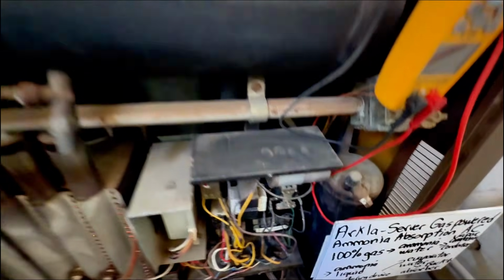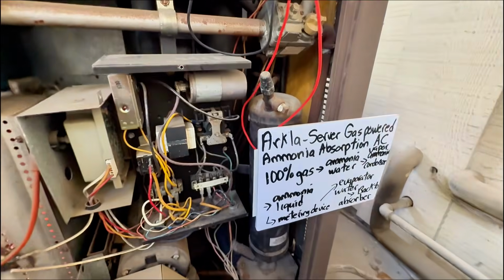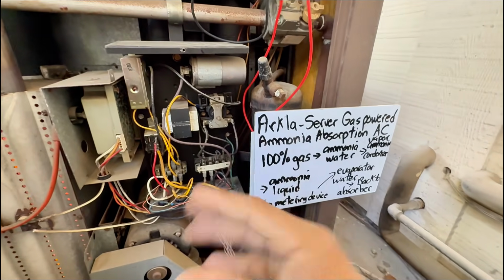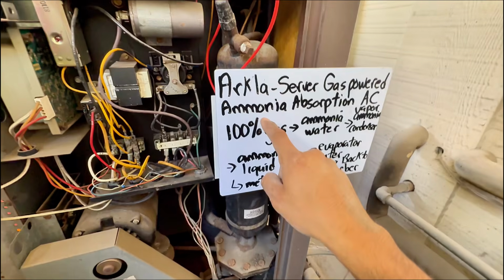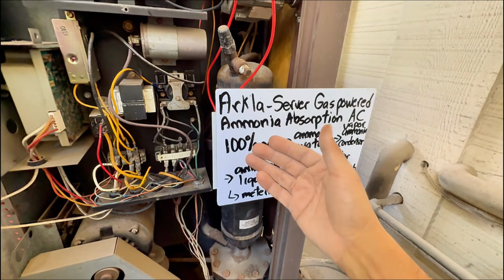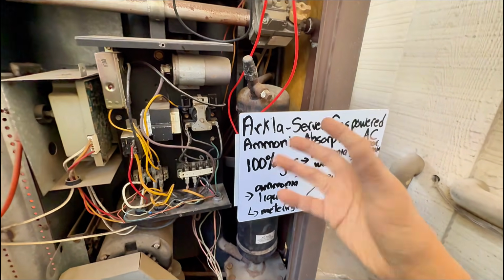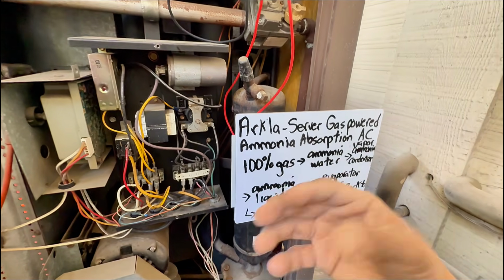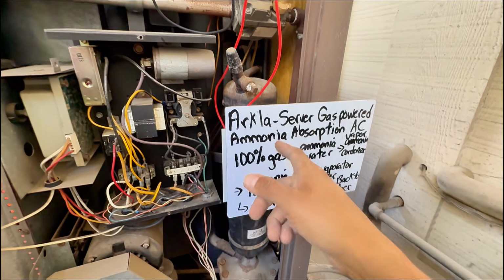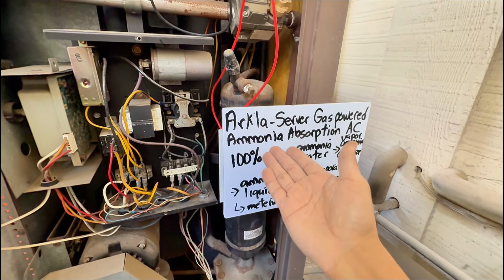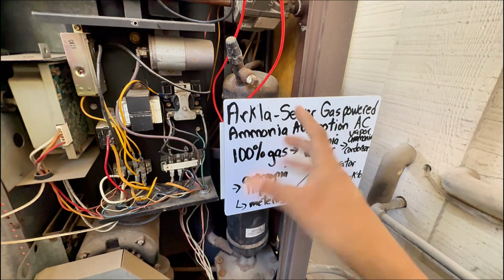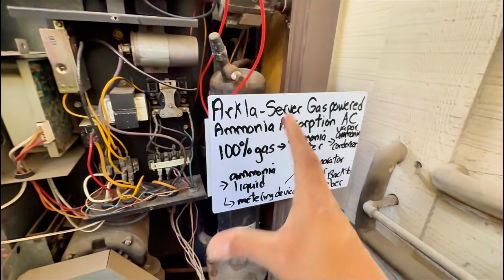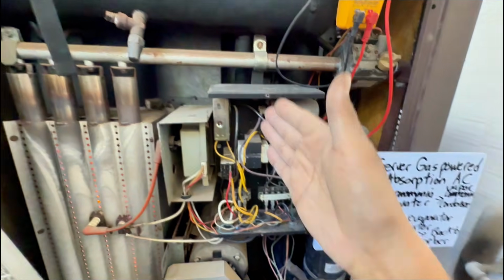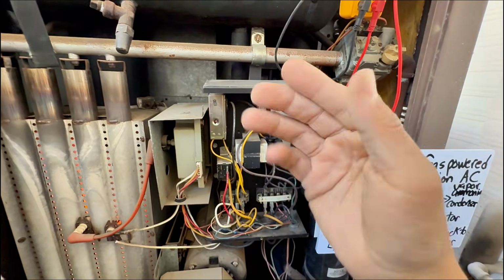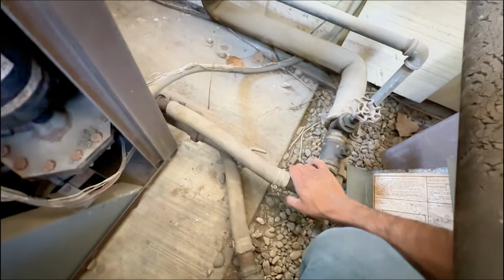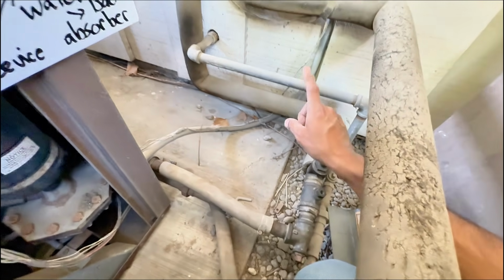And then you got my mess over here. Like I said, it was gonna be a short video, but the way this one works, crazy. It uses ammonia. As you know, ammonia is a refrigerant in the sense that you can manipulate its pressures. We can provide heating and cooling. Now, I'm sure they use this more in commercial. I don't have a lot of experience with this, but I'll explain what I've been able to figure out, okay? Now, this system does not have a compressor. Yep, no compressor, and yet my line right here, and this is my water line going into an indoor coil, it's cold.